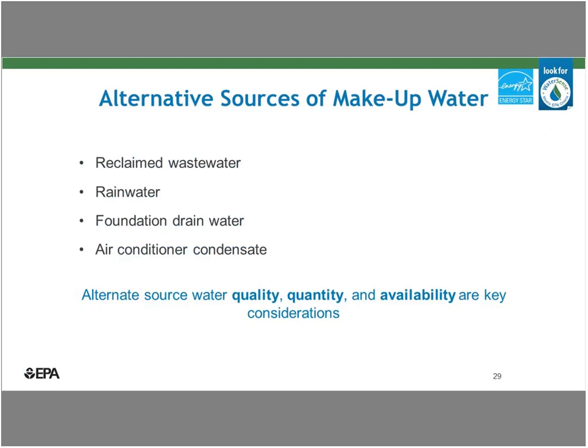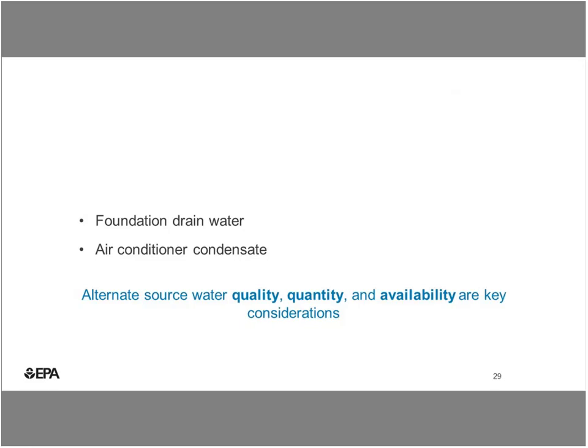Another opportunity to reduce the amount of potable water that you're using in your cooling tower is to identify an alternative source of water that can be used to supplement or replace city water in the makeup line. Some possible sources include reclaimed wastewater, rainwater, foundation drain water, and air conditioner condensate. One thing you want to remember when assessing alternative water sources is that the water quality, quantity, and availability should all be considered. So only use alternative sources when you're able to match the quality of the alternative source to the need of the system. For example, using blowdown water can be challenging because it's high in salts and chemicals, but something like air handler condensate is a great option for cooling towers, and I'll talk about that now.